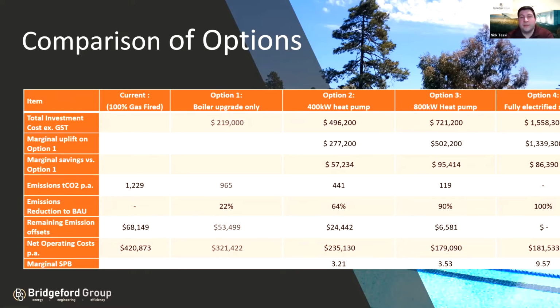Something we also focus on here is marginal uplift. As one of the boilers is at end of life and will be replaced anyway as part of that maintenance upgrade budget, we looked at what the cost uplift was to electrify from the business-as-usual case, and what the payback on that uplift would be. As you can see, there are some pretty attractive figures here because of the high hours of operation proposed for those heat pumps that aren't sitting at peak load.